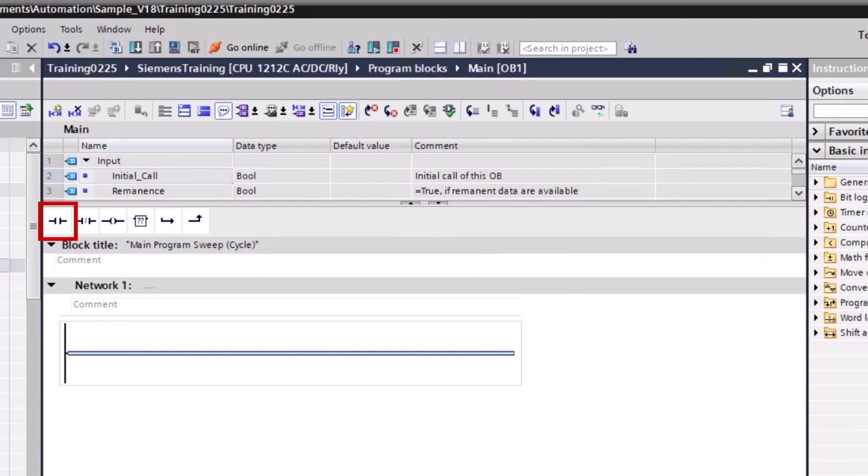The activation of the normally open contact depends on the signal state of the associated operand. When the operand has signal state 1, the normally open contact closes and the signal state at the output is set to the signal state of the input. When the operand has signal state 0, the normally open contact is not activated and the signal state at the output is reset to 0.